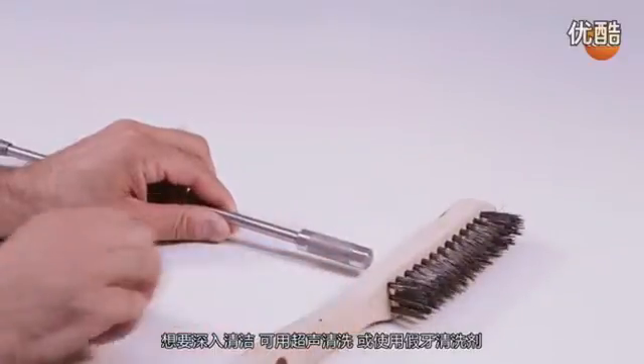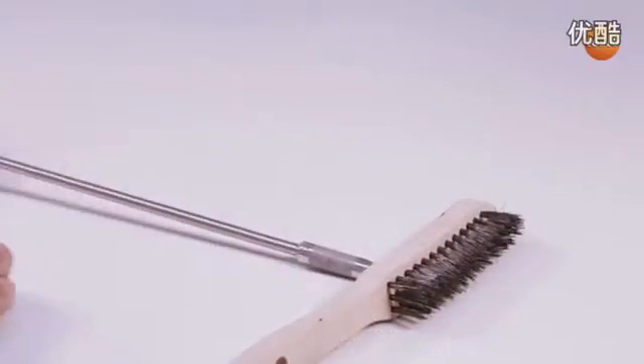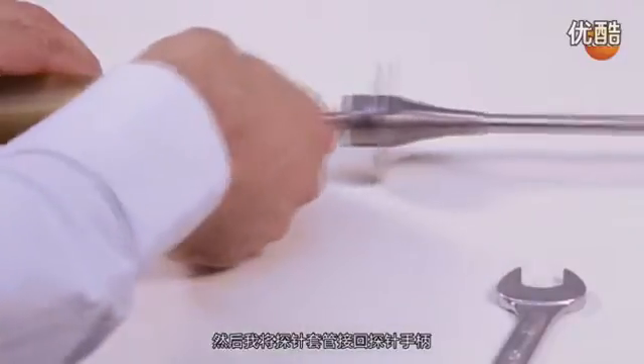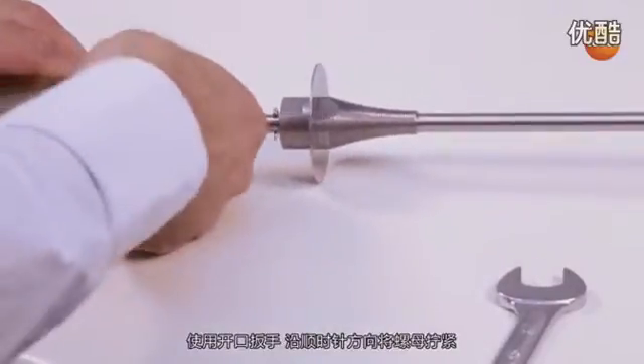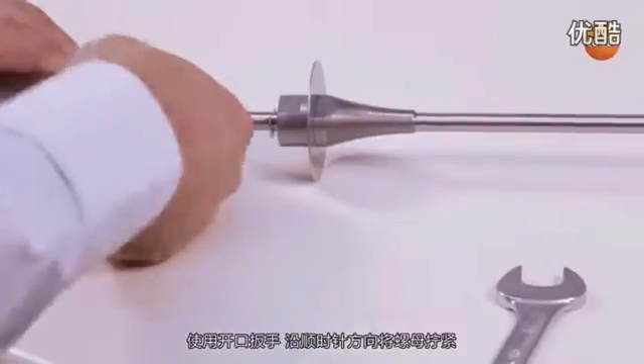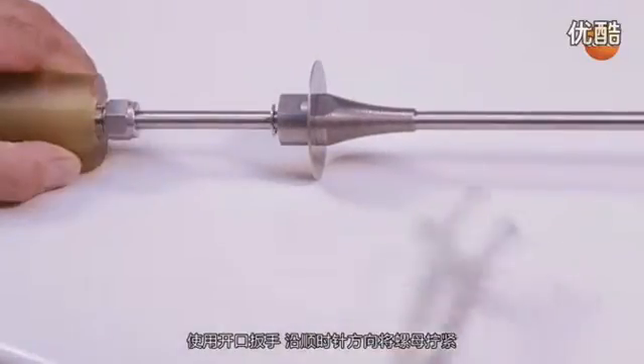I can clean the sinter filter with a wire brush. To clean completely, I can use an ultrasound bath or denture cleaners. I then replace the probe shaft on the probe handle and screw the ring hand tight in clockwise direction with an open-end wrench.